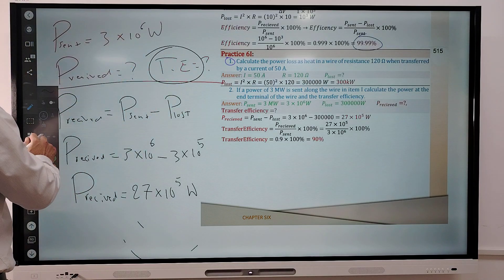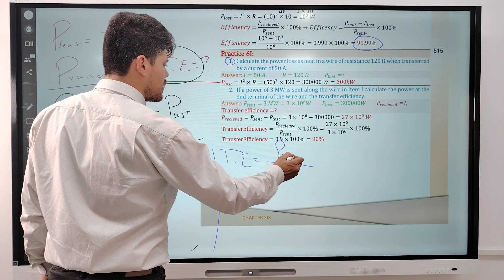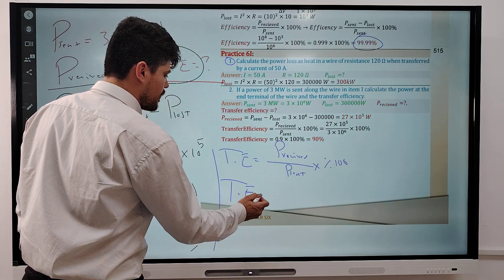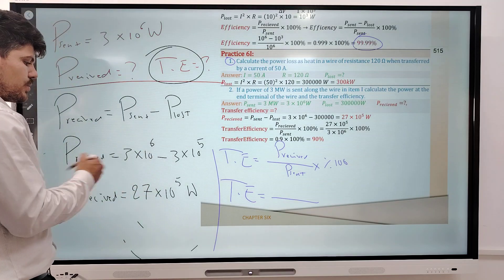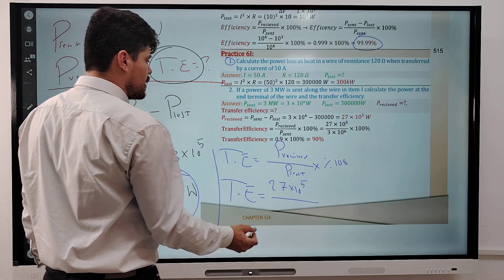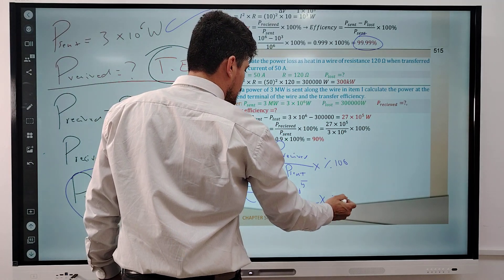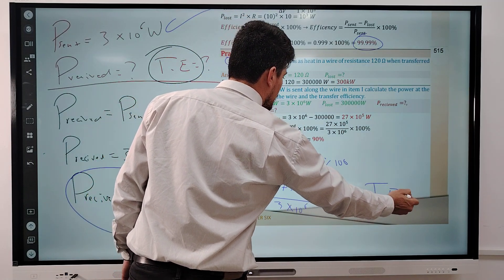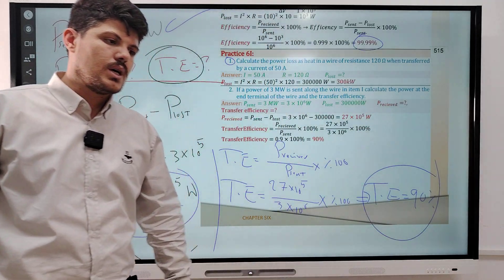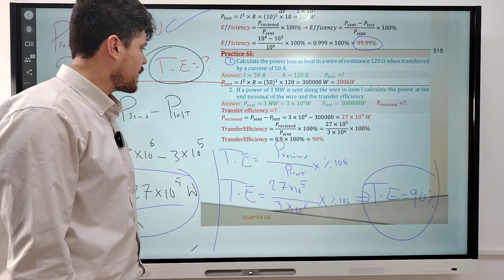The second unknown is the transfer efficiency. Transfer efficiency equals P received divided by P sent times 100%. Replacing: 2.7 times 10 to the 6 divided by 3 times 10 to the 6, times 100%, equals 0.9 times 100%, which equals 90%.